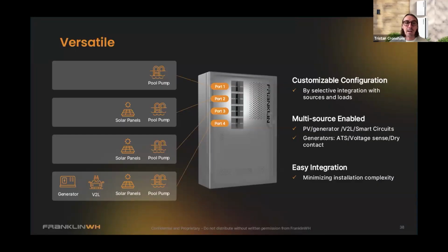And so the critical components or critical loads remain energized throughout the grid outage. That's one use case. You also could connect multiple AC inverters into the A-Hub, and those can be individually controlled, turned on and off in a grid outage.